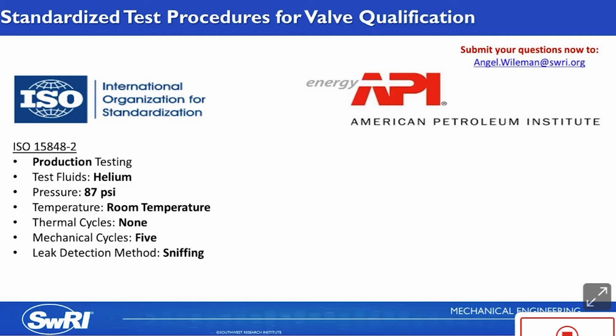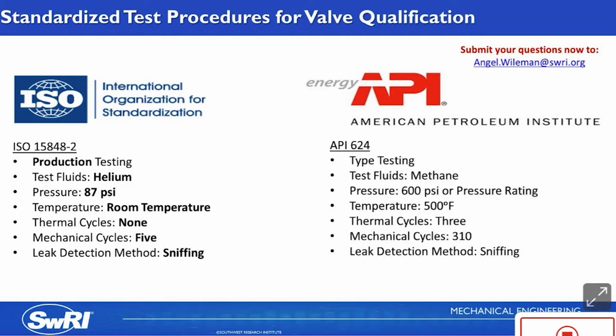And this test is much simpler than the first part of the standard. You use helium test gas at low pressures. There's no thermal cycles. There's only 5 mechanical cycles, and you use the sniffing method to detect leakage. The same general procedures are seen in the API FE test standards, but there are some notable differences. API 624 is type testing of rising stem valves equipped with graphite packing for fugitive emissions.